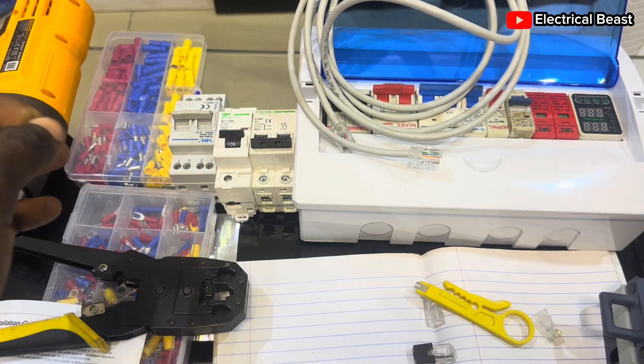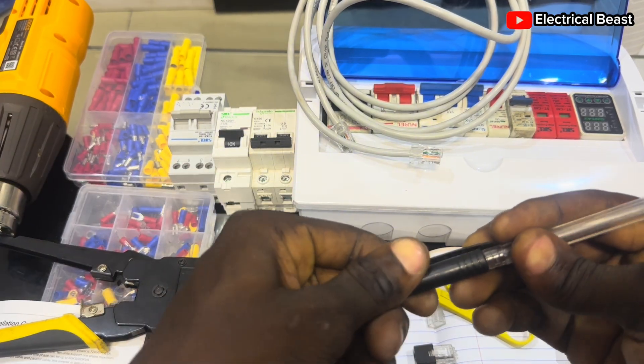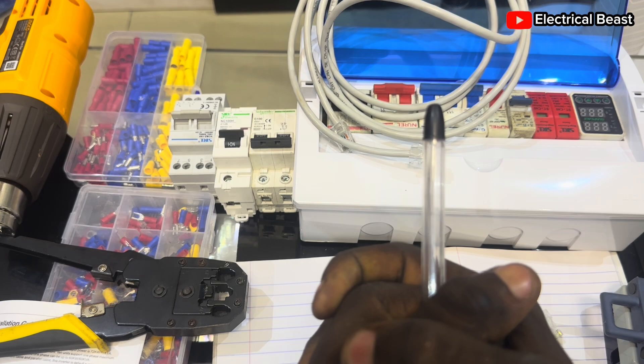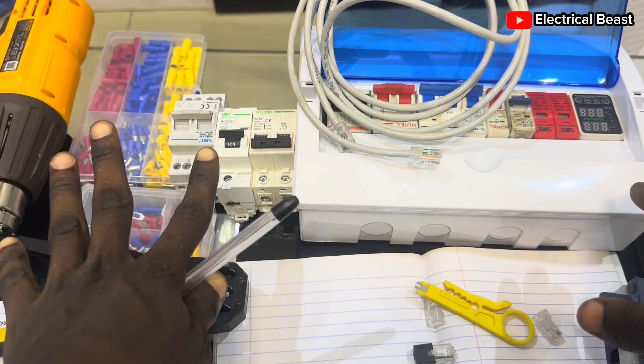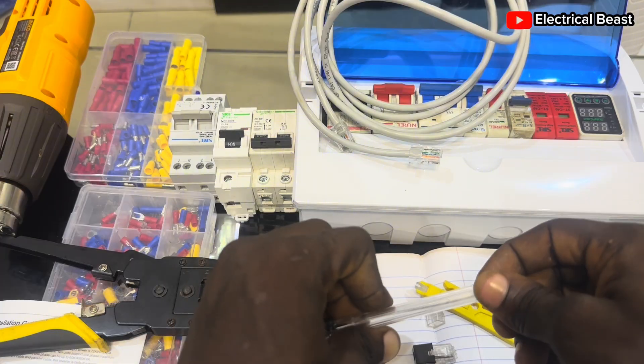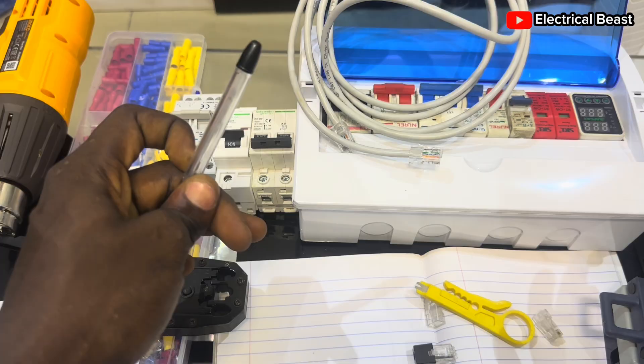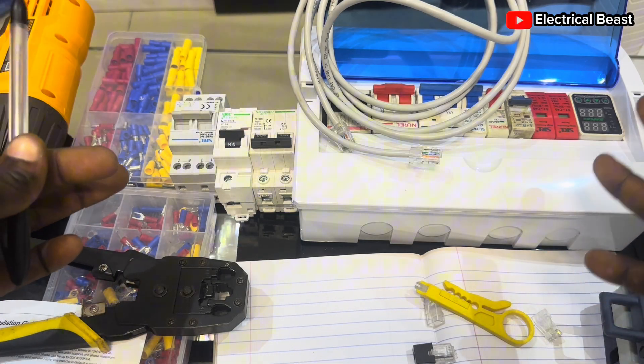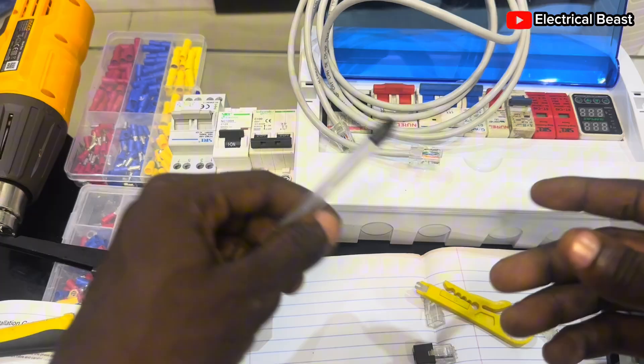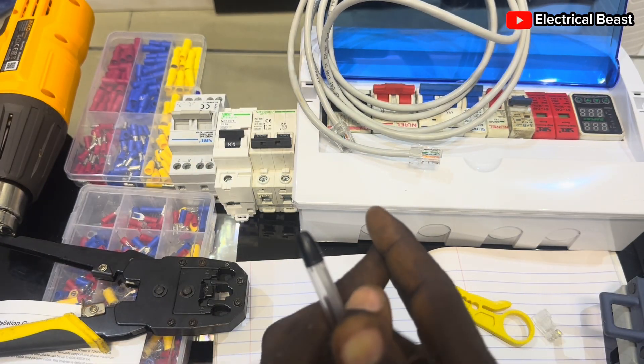One of the ways to curb this is to ensure that our inverter communicates well with our battery. It's very easy when the products are the same brand — a Felicity inverter with a Felicity lithium battery, just use the cable that came with the pack and it establishes the connection seamlessly. Same with CNEW to CNEW. But the big question is: how do you communicate a Felicity inverter to a CNEW battery, or mix different brands in your setup?